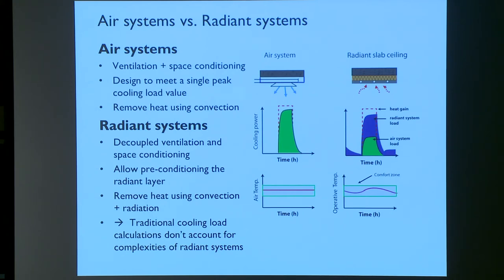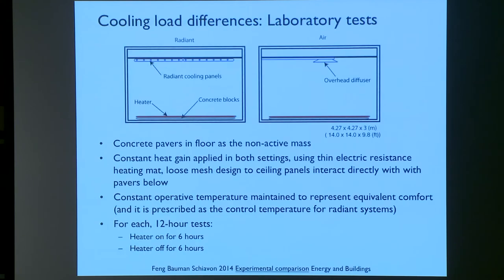One of the challenges we found, though, is that traditional recommended methods for calculating cooling loads in buildings were not accounting for some of the unique characteristics of radiant systems, where they're actually taking energy out of the building not just from the air - making the air do all the work - but also taking out a radiant component. So we've been doing a lot of work on radiant systems.